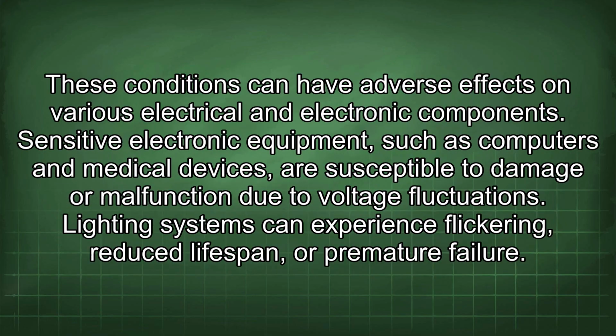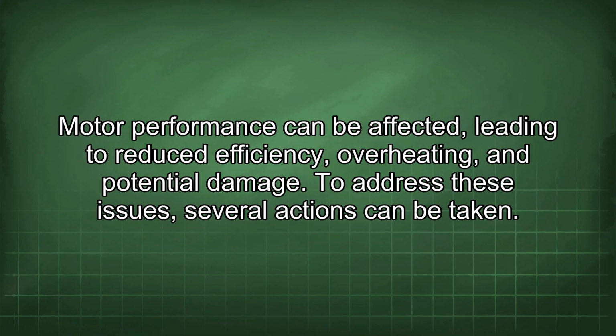These conditions can have adverse effects on various electrical and electronic components. Sensitive electronic equipment, such as computers and medical devices, are susceptible to damage or malfunction due to voltage fluctuations. Lighting systems can experience flickering, reduced lifespan, or premature failure. Motor performance can be affected, leading to reduced efficiency, overheating, and potential damage.